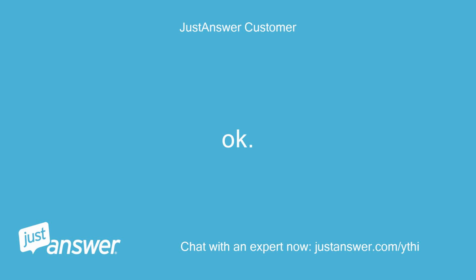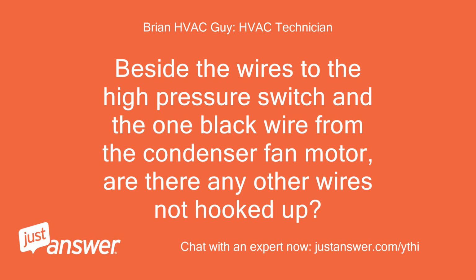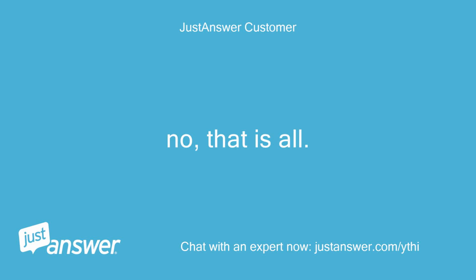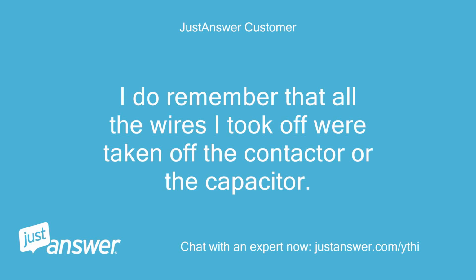Okay. Let's have it. Beside the wires to the high pressure switch and the one black wire from the condenser fan motor, are there any other wires not hooked up? No, that is all. I do remember that all the wires I took off were taken off the contactor or the capacitor.